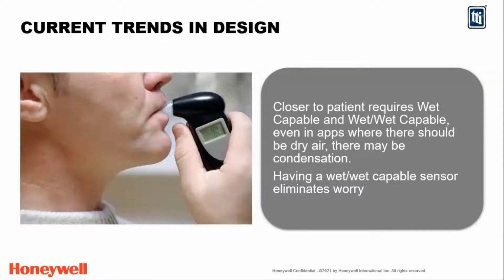We're seeing that a lot of our end customers are looking to get closer to the patient to take their measurements. The reason for that is it's a better measurement. You don't have a lot of errors introduced by long tubing. If you're trying to measure something 6 feet back in a ventilator, as an example, it's not the same measurement as if you're at the mask because of the pressure drop. When somebody breathes, it's not going to give you the same accuracy. So they're trying to get closer and closer to the patient to improve the accuracy.